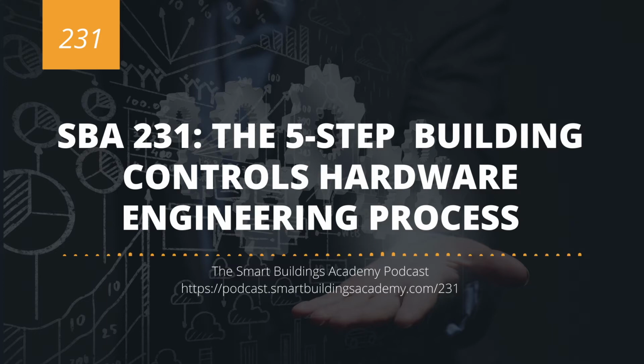you want to dive into what are the required pieces of hardware, manufacturers, what related divisions are quoted in this spec, because those related divisions could drive your hardware. Like if it's related to fire alarm or lighting and you need to provide dry contact IO, that's important to understand, because then that will dictate how you build out your hardware, how you build out your controller layouts, and potentially how you build out your panel layouts. So that's general section 1.